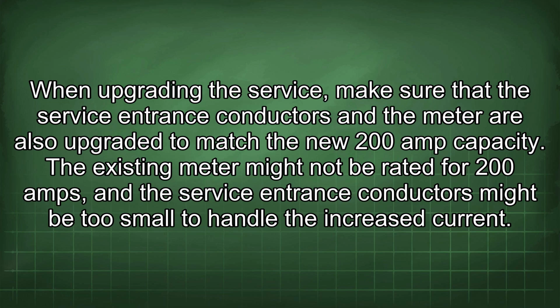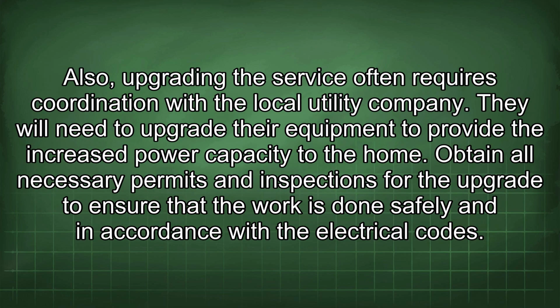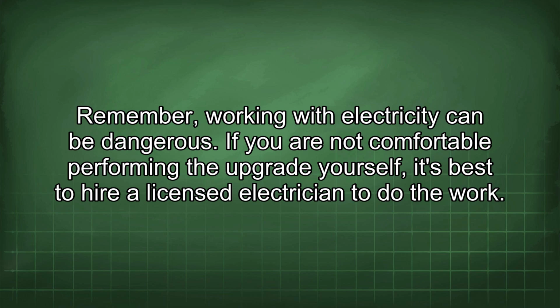When upgrading the service, make sure that the service entrance conductors and the meter are also upgraded to match the new 200 amp capacity. The existing meter might not be rated for 200 amps, and the service entrance conductors might be too small to handle the increased current. Also, upgrading the service often requires coordination with the local utility company. They will need to upgrade their equipment to provide the increased power capacity to the home. Obtain all necessary permits and inspections for the upgrade to ensure that the work is done safely and in accordance with the electrical codes. Remember, working with electricity can be dangerous. If you are not comfortable performing the upgrade yourself, it's best to hire a licensed electrician to do the work.